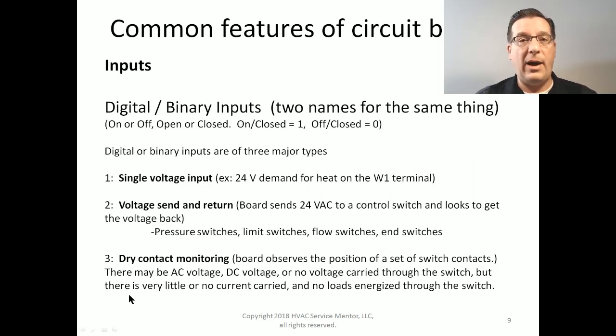And the third type of binary switching is called dry contact monitoring. Now, in residential operations, so far, there's not a whole lot of dry contact monitoring going on, but the technology is beginning to enter the industry. And I predict that within the next 3 to 5 years, we're going to be seeing a lot more dry contact monitoring happening in residential equipment. It happens all the time in commercial equipment, and the technology tends to filter down into residential.